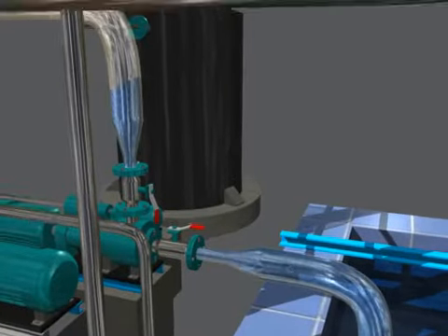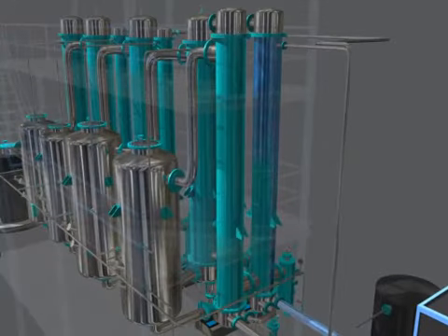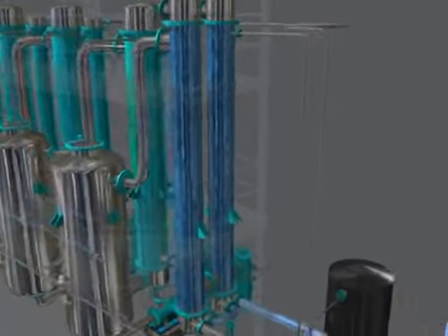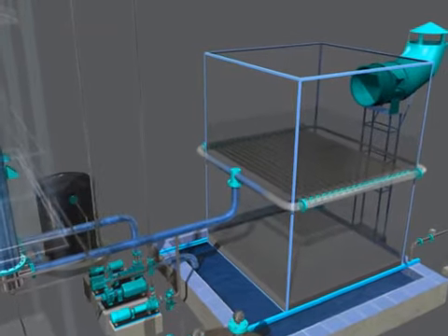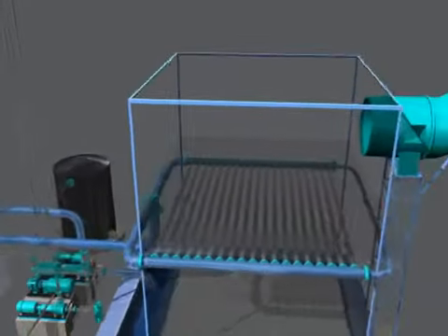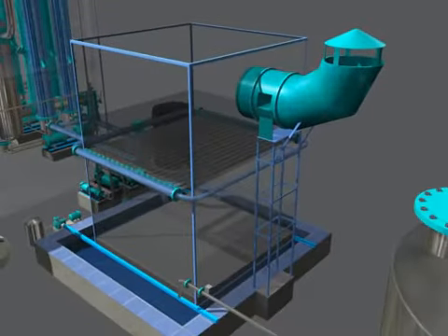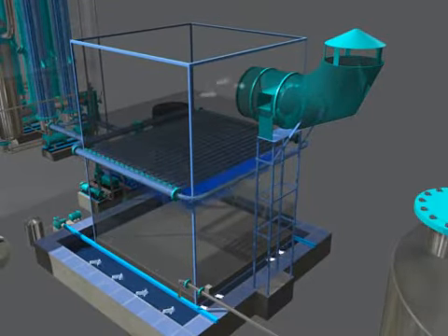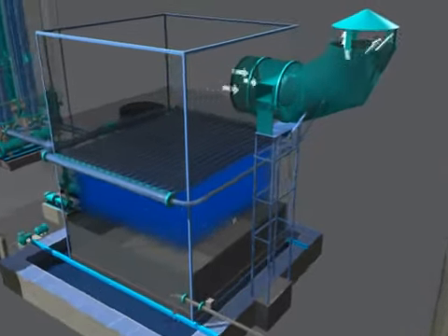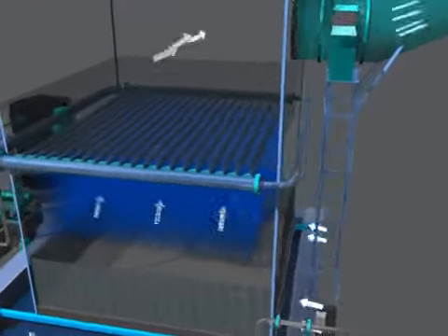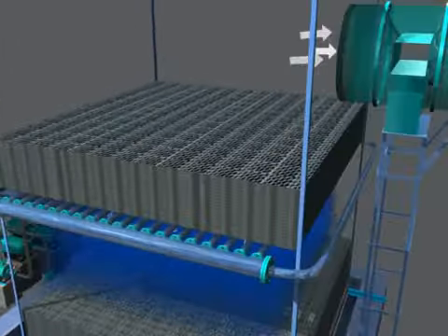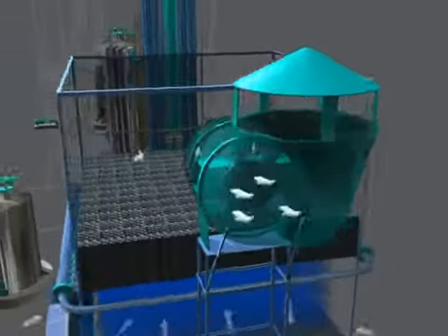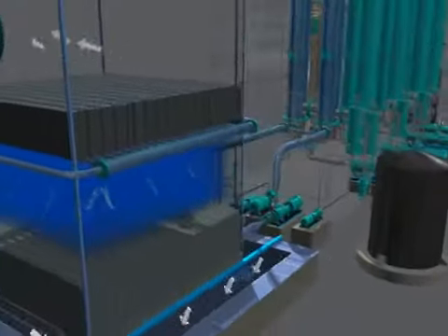The condensers are used to condense vapors in the last stage of the evaporator to maintain the required vacuum in the system. During the process, the sensible heat of the liquid is used to evaporate the water in the feed, which comes to you free of cost, saving a lot of steam. The hot liquid is sprayed in the adiabatic evaporator through evaporative fills and gets cooled by the fresh draft of cold air. This method not only saves steam, but also removes the requirement of a cooling tower from the system.